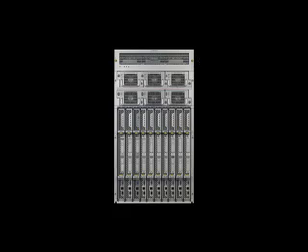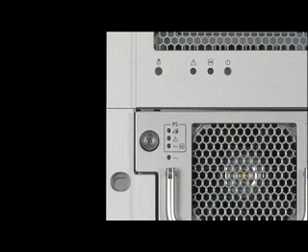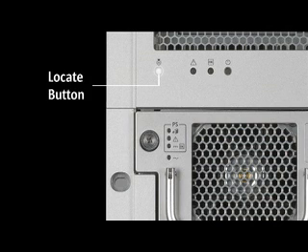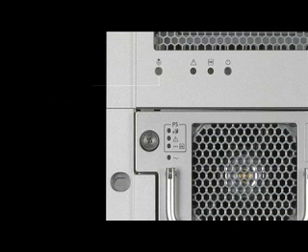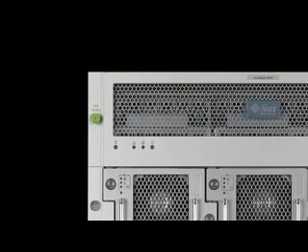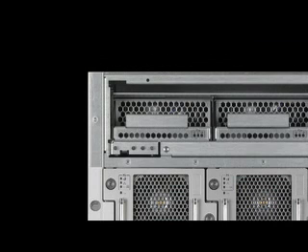It allows the user to power the chassis on, but not off, and to review the service LED indicators. The indicators are power button on, but not off, locator button LED to identify the system at the chassis level, OK normal LED, which indicates power status, fault LED, which indicates attention is needed by a component in the enclosure. To access the fans behind the front grille, unscrew the green captive screws on either end. The front fan modules provide cooling to the PCI Express modules.